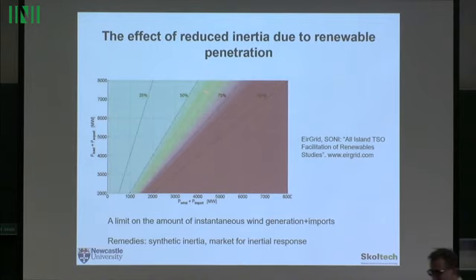This is demand, and they reckon about 50% is safe operation. So at night, especially when wind was strong and demand was low, wind generation would exceed 50% of demand, and they had to spill it because it was dangerous. At the moment, I think they have additional measures, bringing it up to 60 or 70%, but not more, because then inertia would be low. If you have an event and drop something, the nadir would be very low, and it can even lead to frequency collapse, basically a blackout.